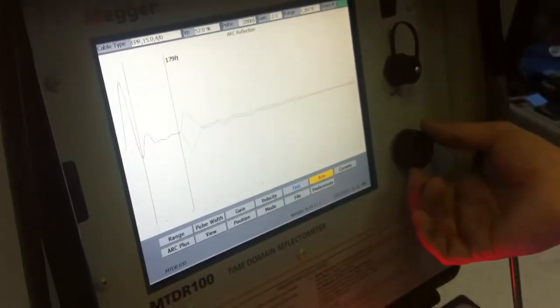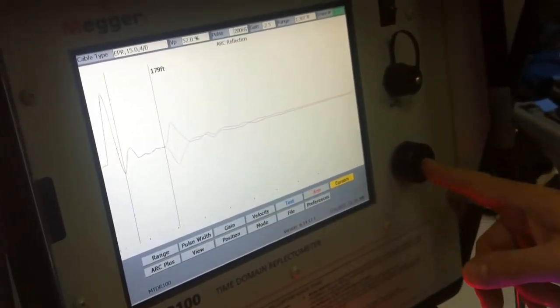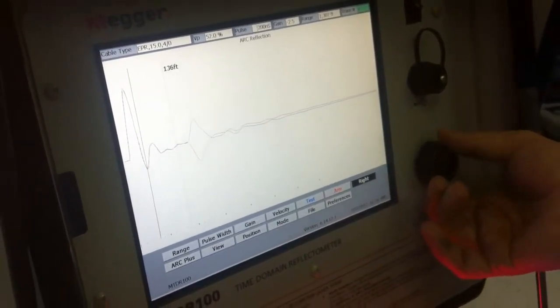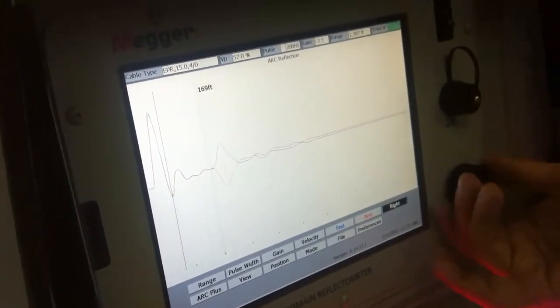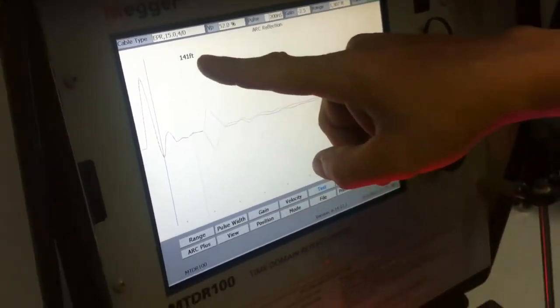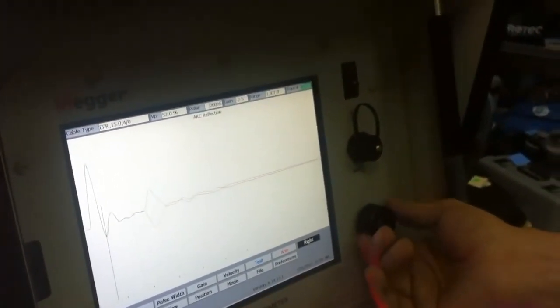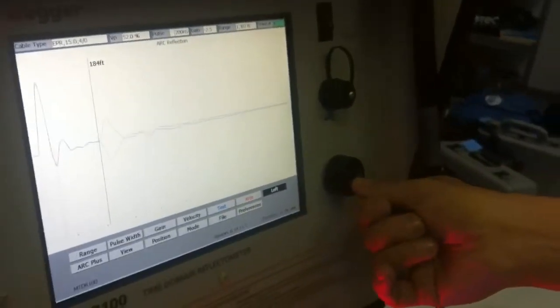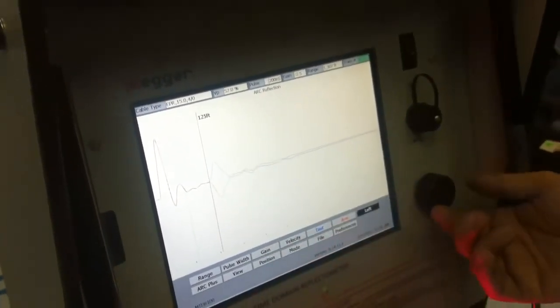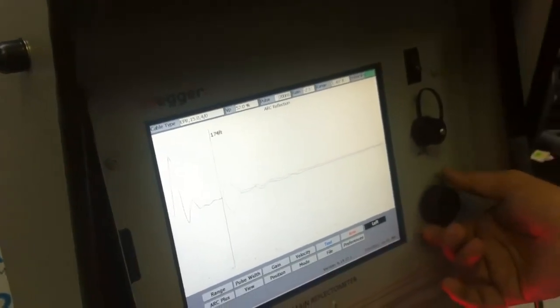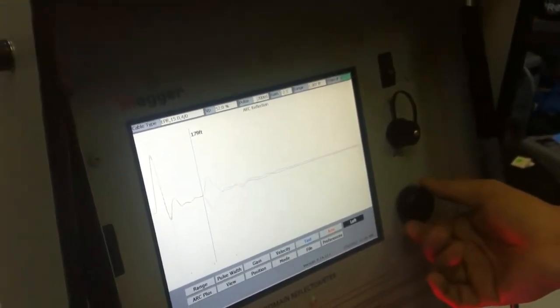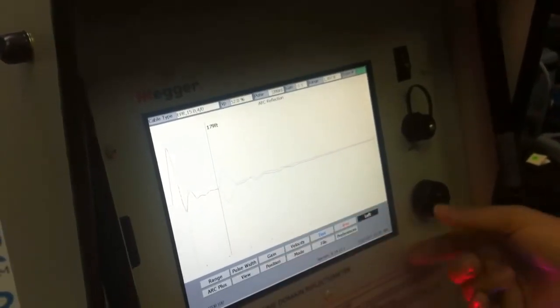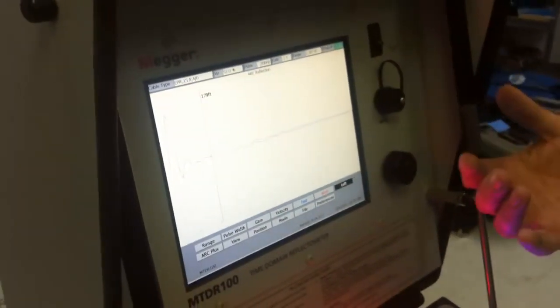If we want to control our cursors, we simply rotate over to cursor, depress once. We have access to the right cursor. Notice that the position of the cursor is clearly spelled out in feet. If I wish to adjust or move my left cursor, I merely depress my knob one more time, activate my left, and I can always take measurements between these 2 points. For normal operation, this will be preset by Protec, and your left cursor will be at the position of the end of your output test lead.